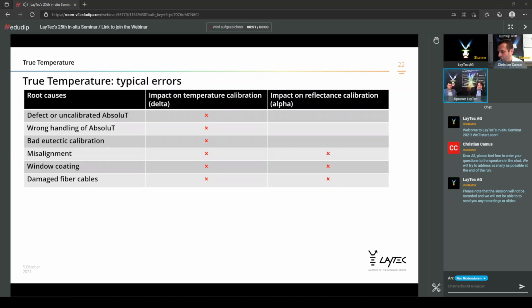With a damaged fiber cable, it's easy to understand that this will have a direct impact on the initially calibrated transmissivity of this cable, possibly for both the light source cable as well as the detector cable. Such an impact on the transmissivity will directly affect both the temperature calibration, the delta calibration, as well as the alpha calibration when you do reflectance calibration. Damaged fiber cables do not mean that in every case the transmission is immediately cut down to 0%. It's more that the transmissivity is no longer constant, fluctuates, and is very sensitive to vibration, motion, or even small hits.